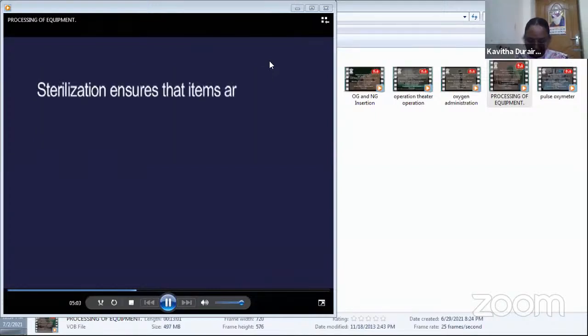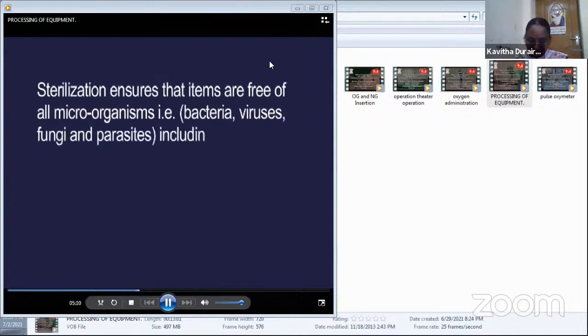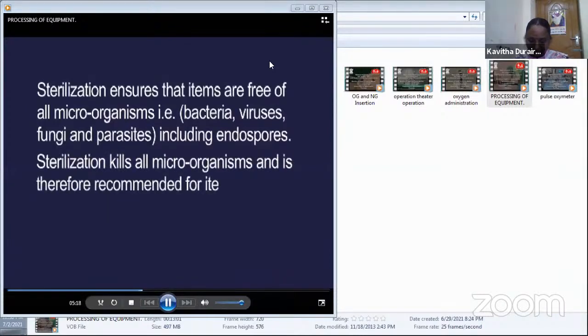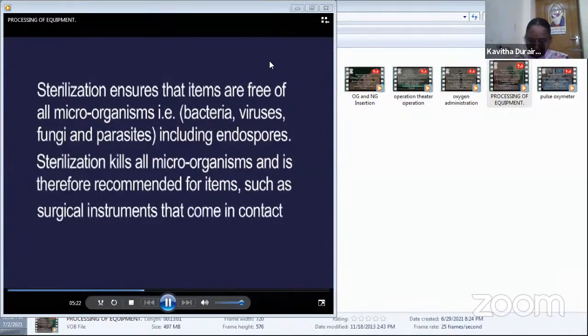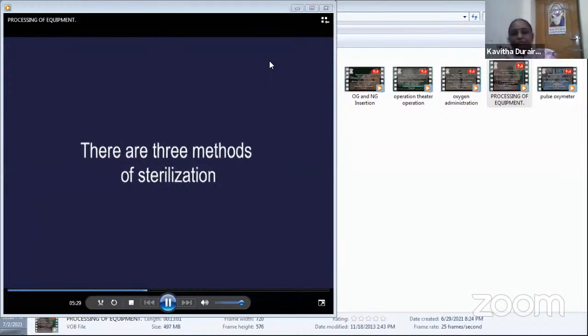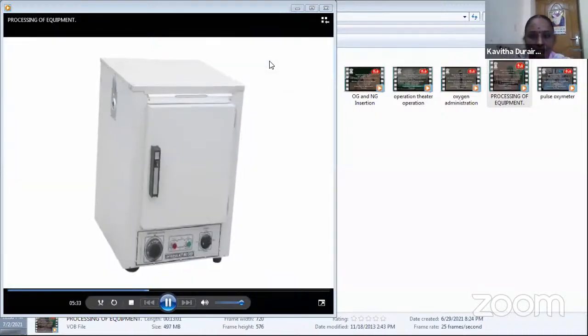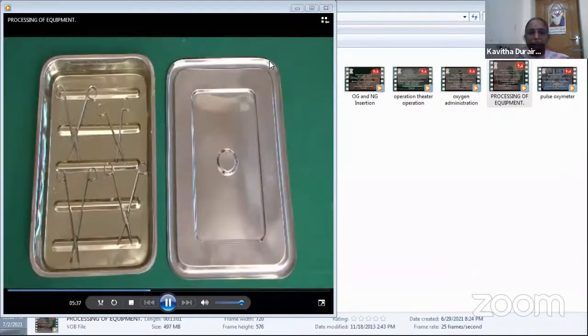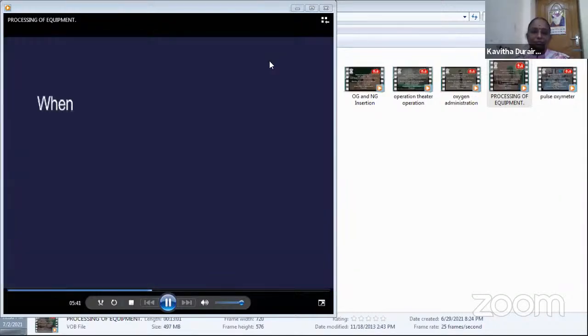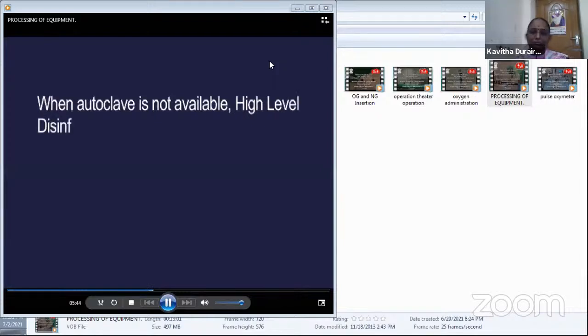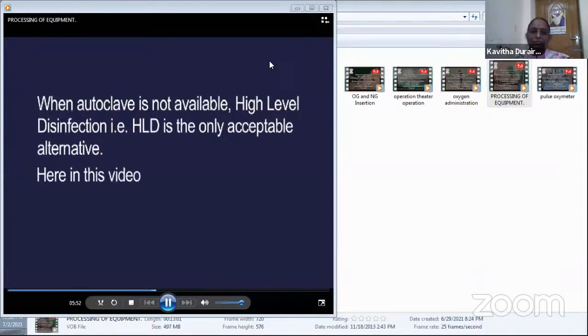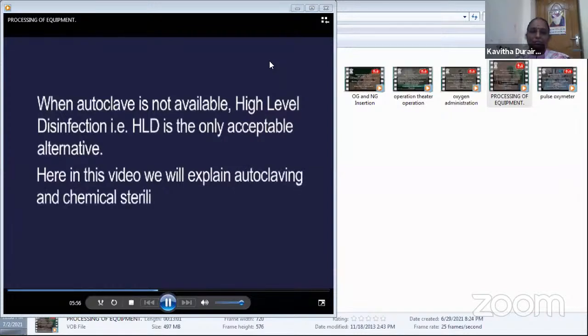Sterilization ensures that items are free of all microorganisms, that is, bacteria, viruses, fungi, and parasites, including endospores. Sterilization kills all microorganisms and is therefore recommended for items such as surgical instruments that come in contact with the blood or tissues under the skin. There are 3 methods of sterilization: steam sterilization by autoclave, dry heat sterilization, that is, electric oven, and chemical, that is, cold sterilization. When an autoclave is not available, high-level disinfection, that is HLD, is the only acceptable alternative. In this video, we will explain autoclaving and chemical sterilization.